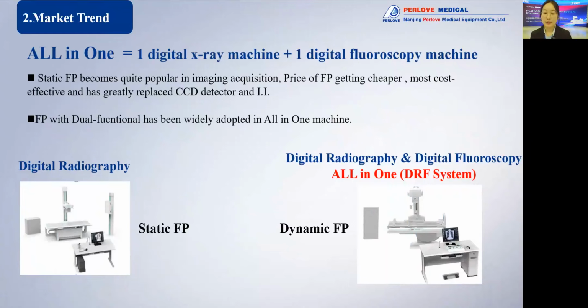And we know that the flat panel detector with dual functions has been widely adopted in all-in-one machines. Look at the pictures below. The left is our digital radiography. It is equipped with our static flat panel detector. However, our all-in-one machine is equipped with our dynamic flat panel, which means it can do both the radiography and the fluoroscopy.